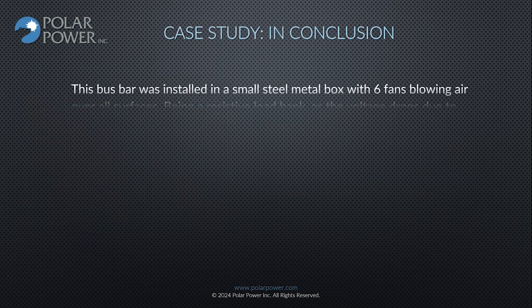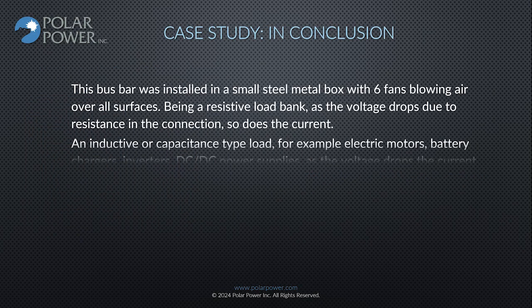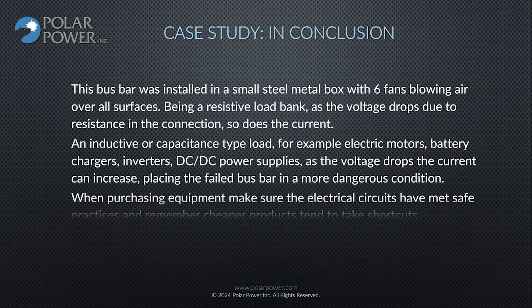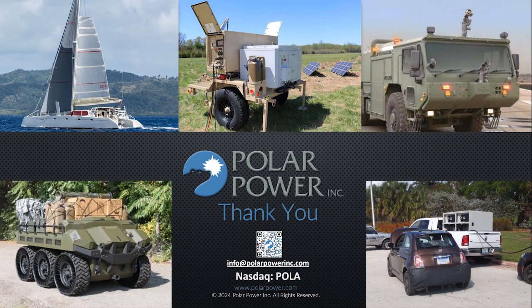In conclusion, this bus bar was installed in a small steel metal box with 6 fans blowing air over all surfaces. Being a resistive load bank, as the voltage drops due to resistance in the connection, so does the current. With an inductive or capacitance type load, for example electric motors, battery chargers, inverters, DC to DC power supplies, as the voltage drops the current can increase, placing the failed bus bar in a more dangerous condition. When purchasing equipment, make sure the electrical circuits have met safe practices, and remember, cheaper products tend to take shortcuts.